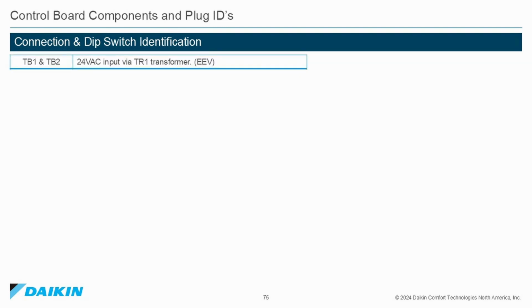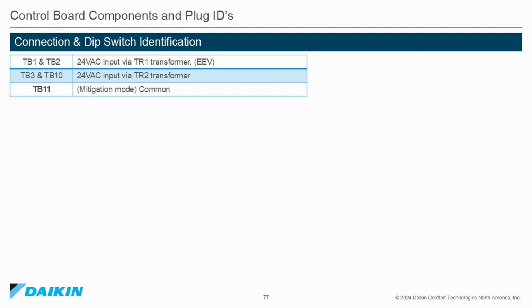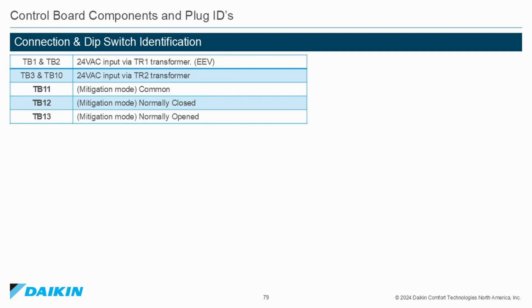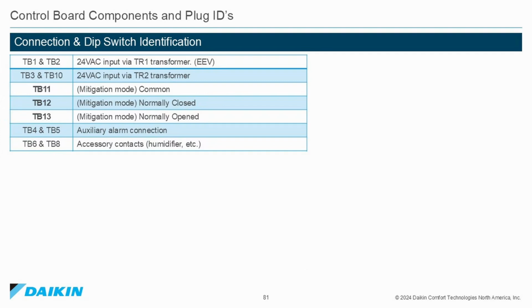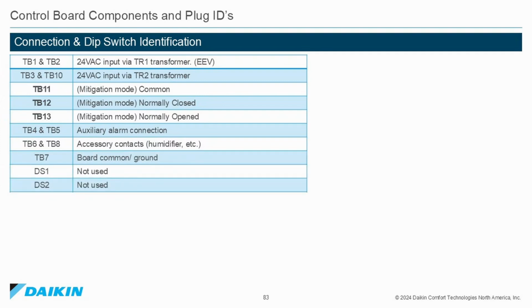TB1 and TB2 are the 24-volt input via transformer TR1 for the electronic expansion valve. TB3 and TB10 are the 24-volt input coming from transformer TR2. TB11, mitigation mode common. TB12, mitigation mode normally closed. TB13, mitigation mode normally opened. TB4 and TB5, auxiliary alarm connection. TB6 and TB8, accessory contacts for humidifier, etc. TB7, board, common, ground. Dip switch 1 and 2 are not used.